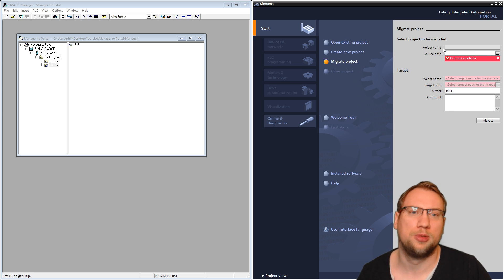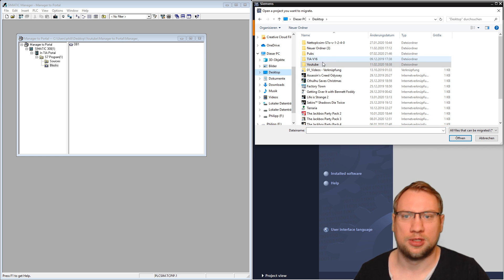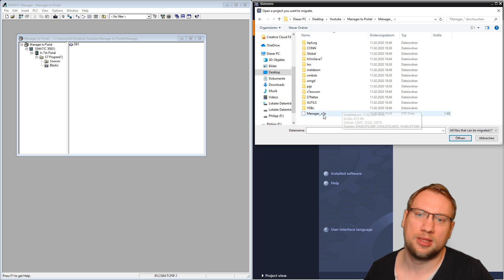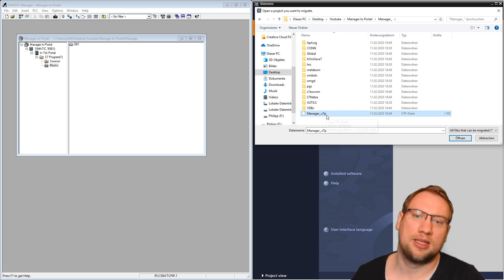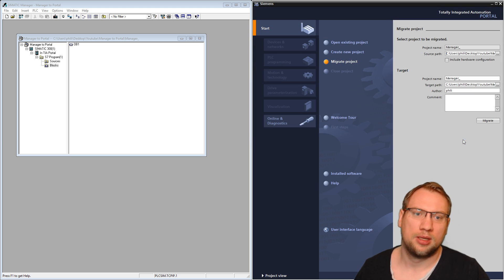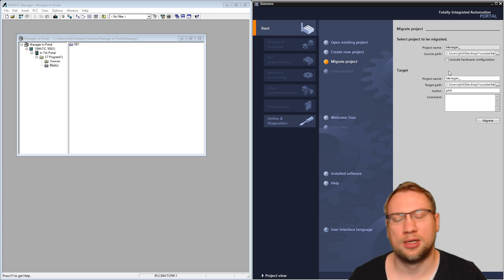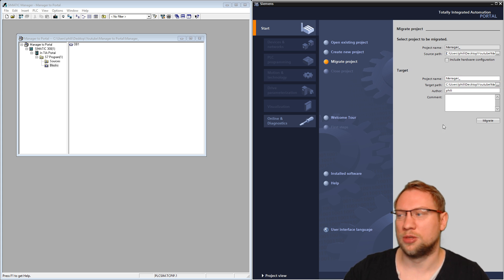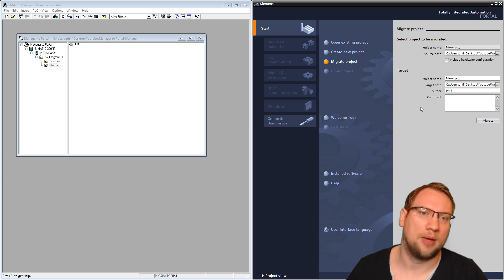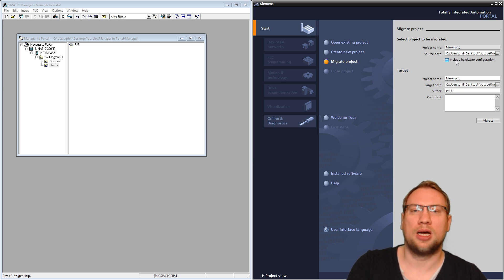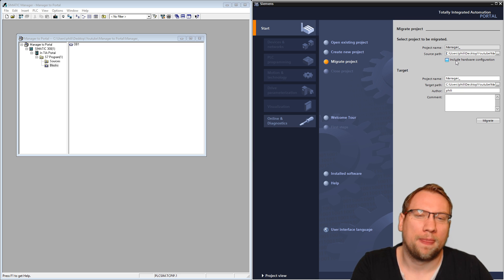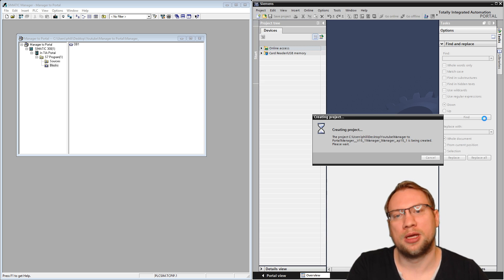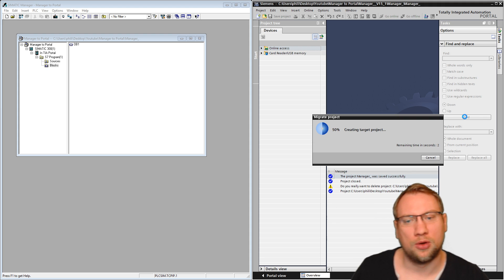I can search for the project. I've saved it here on my desktop in a folder called 'YouTube Manager to Portal.' There it is — the project folder. I select the .s7p S7 project file and click Open. TIA Portal automatically decides the save name and path, though you could choose a different path. There's one checkbox that says 'Include hardware configuration' — I'll do it now without including it, to see what happens. I click Migrate.